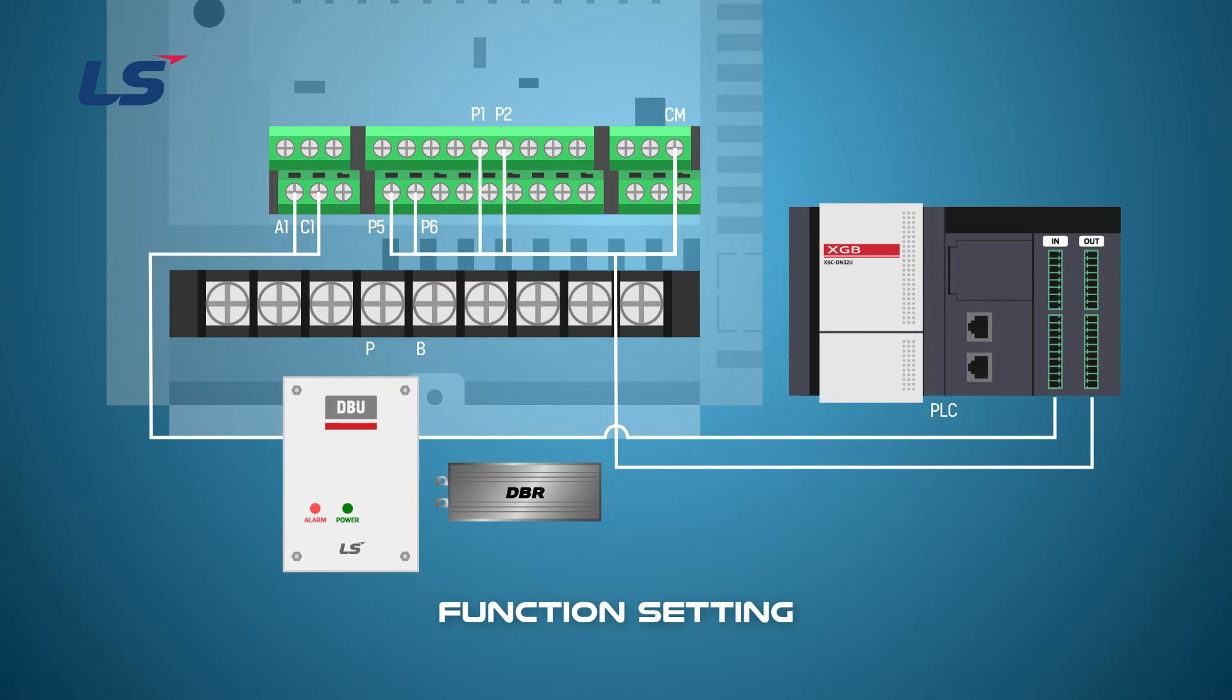In case of separately installing the brake unit, install it at the P and N stages and install the braking resistor. Please refer to the inverter manual for the specifications of the braking resistor and braking unit according to the product capacity.